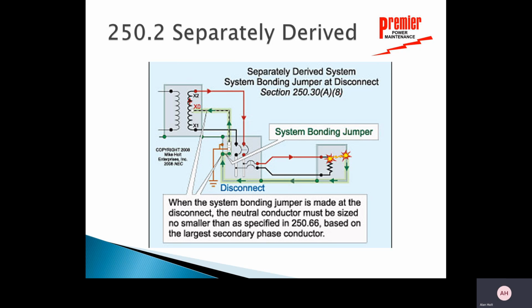I can see that I've got the separately derived system. There's my transformer, separately derived. There's my hot leg. Here's my other hot leg. And hopefully you knew this, but the center point, the center tap of that transformer is where I have my neutral, okay? So here's 120 volts, here's 120 volts, and across the whole pair, there's my 240.